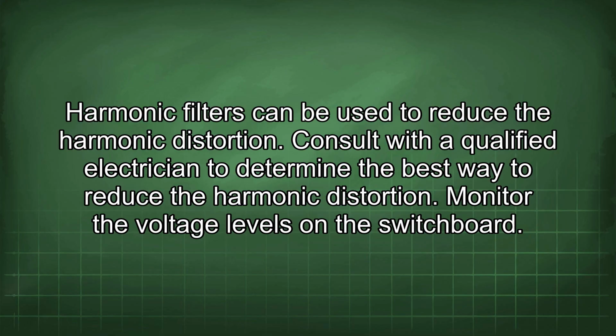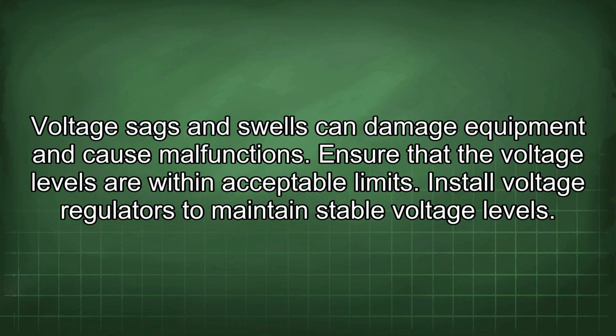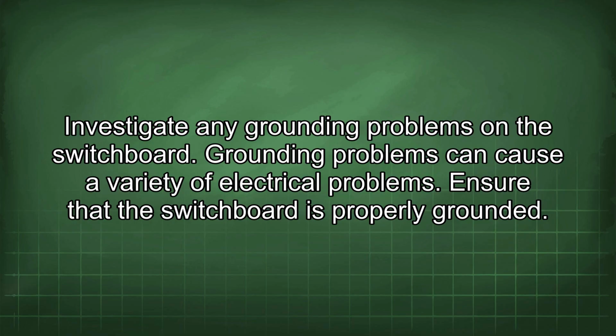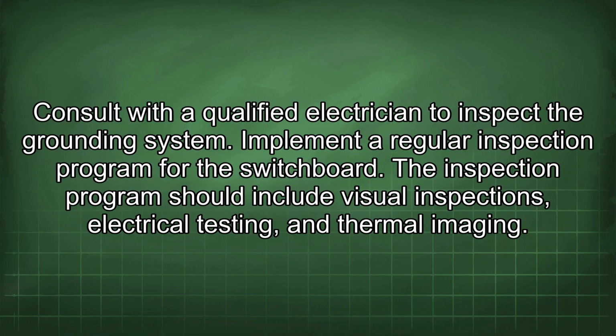Monitor the voltage levels on the switchboard. Voltage sags and swells can damage equipment and cause malfunctions. Ensure that the voltage levels are within acceptable limits. Install voltage regulators to maintain stable voltage levels. Investigate any grounding problems on the switchboard. Grounding problems can cause a variety of electrical problems. Ensure that the switchboard is properly grounded. Consult with a qualified electrician to inspect the grounding system.